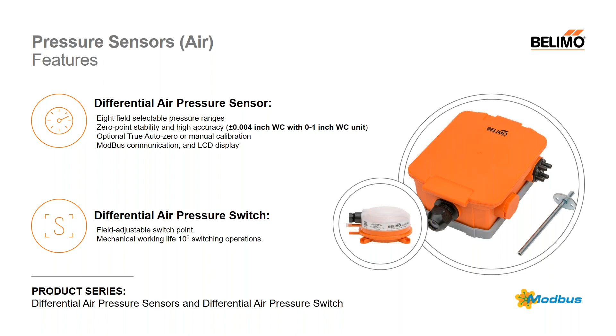These units are also extremely accurate, with a plus or minus 0.004 inch water column accuracy on the units that have a pressure range of 0 to 1 inch water column. Also, as I spoke to before, we offer what we call a true auto zero function that calibrates the unit automatically every 10 minutes. These sensors are available with multiple outputs, including Modbus protocols, and we also offer these units with an optional LCD display.